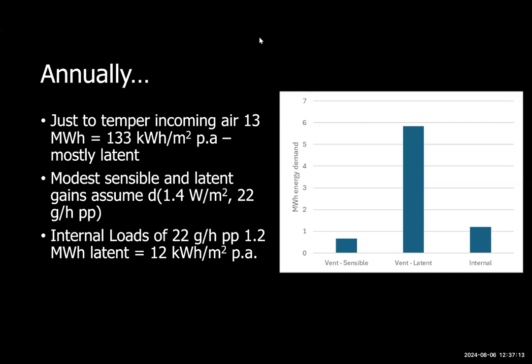But basically we can assume that we have about 22 grams per hour per person. If you crunch these numbers through, we get to about 1.2 megawatt hours, or 12 kilowatt hours per meter square per year. The bar chart here is just showing that that's still quite a small proportion compared to the amount of moisture we need to remove from the air into the building just to avoid high humidity. In other words, the moisture we need to worry about is mostly in the outside air, and only a small proportion is released by people and their activities in the space.